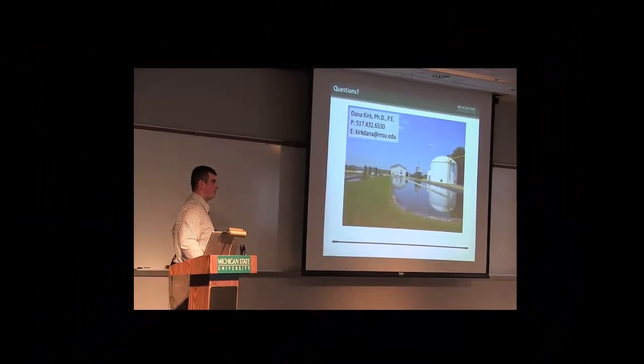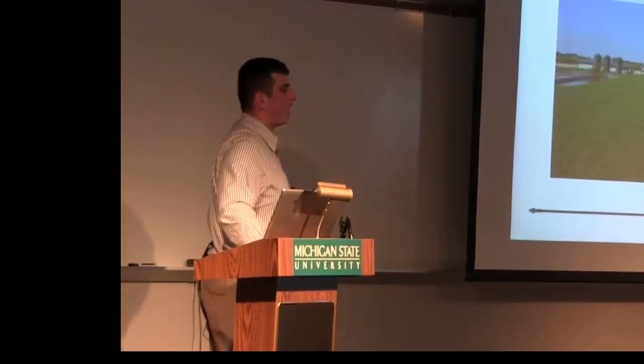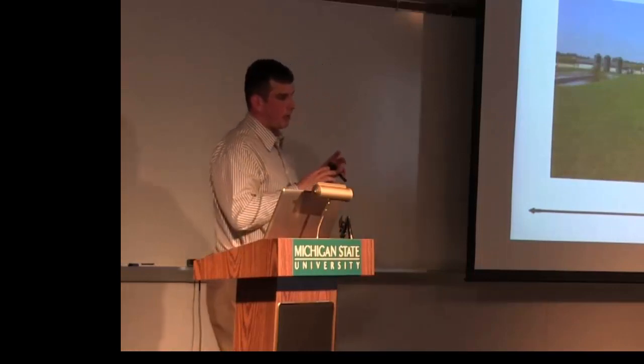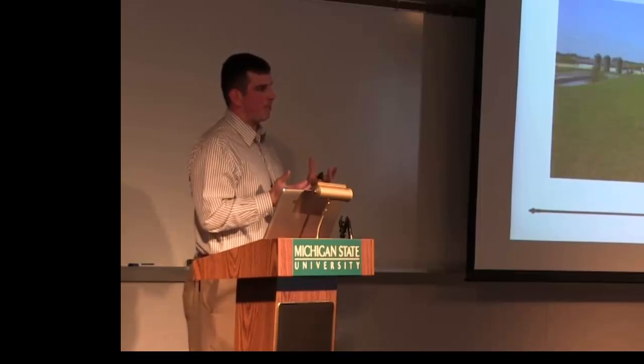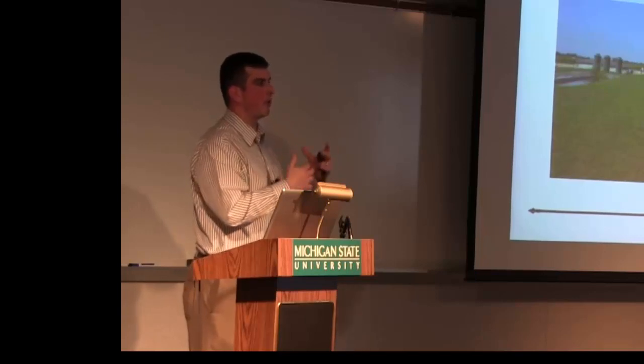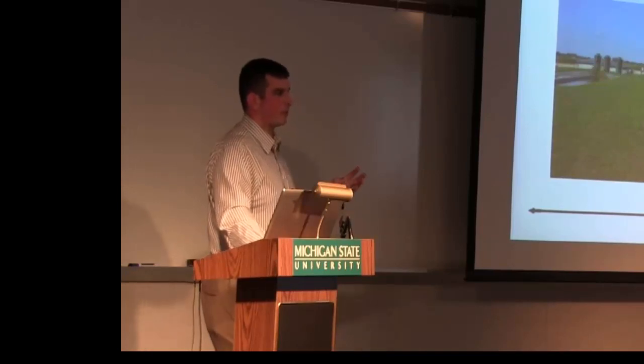What is the city of Granville doing with the egg that they have? What does that produce? I don't know what it produces. It is a different configuration. It is a complete mixed digester, but by having that egg shape, they're able to get more natural mixing and more benefit of the mixing of just the pumps, and so they don't have to have any internal agitators or mixers in that system. It's a very traditional design for wastewater treatment plants. As far as what their energy outputs are, I don't know. I've never visited the site, so I'm not sure what performance is on it as well. I was there before it was finished and operating.